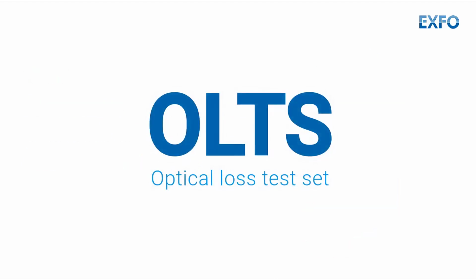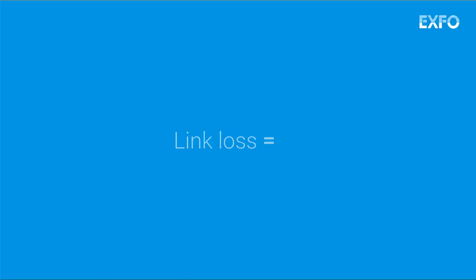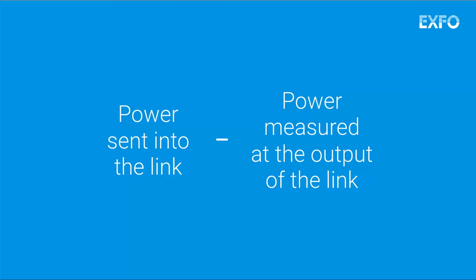An OLTS, short for optical loss test set, doesn't measure loss. It actually measures power at a given point. It calculates loss by comparing this power to what is called a reference power value. Hence the importance of performing a proper referencing on your OLTS.